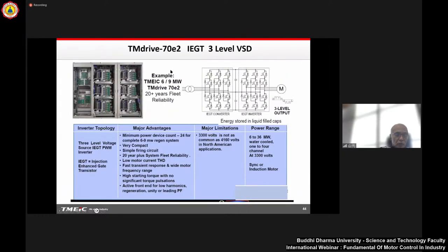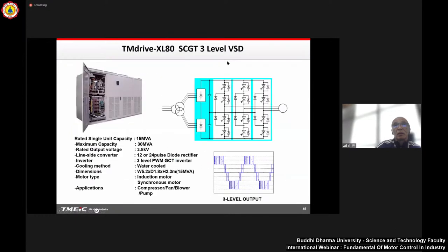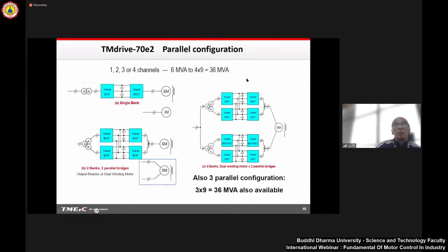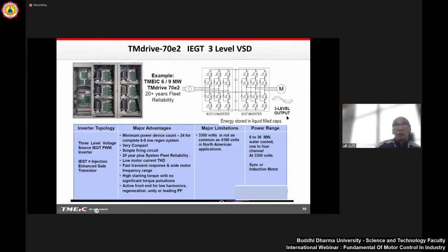This next one is TM drive 70E2 IEGT three level VSD, variable speed drive. This one has a three level NPC IEGT converter section on the converter side, and this is for the inverter side. This three level unit is most likely used for steel rolling mill drives, about 10 megawatt class motors with very, very fast response.